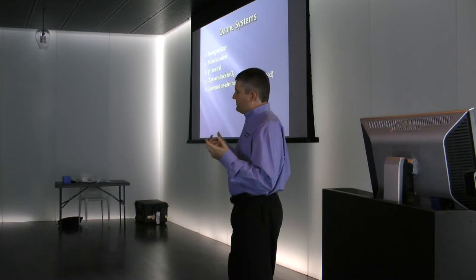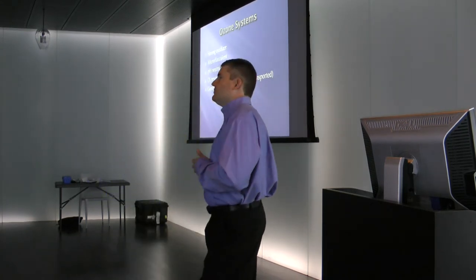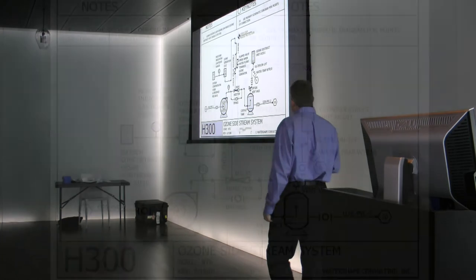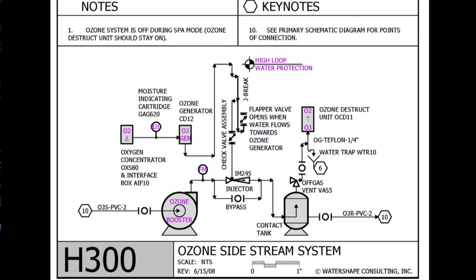And as it reacts, the ozone reverts very quickly back to oxygen. And you can strip off that oxygen and strip off any excess ozone and run it through a destruct unit. I think I have a schematic diagram of this. In this case, we're using a pump and then we're injecting the ozone in, and we're running it through this contact tank.